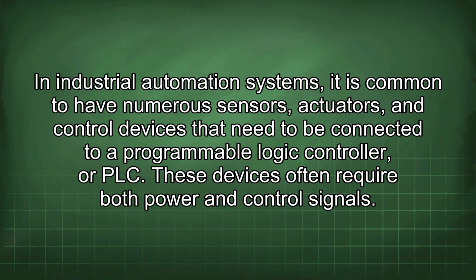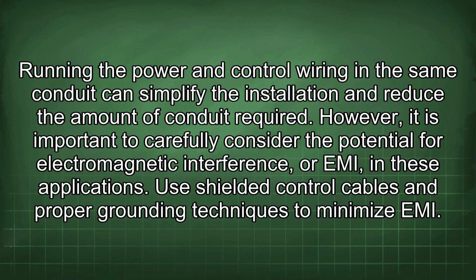In industrial automation systems, it is common to have numerous sensors, actuators, and control devices that need to be connected to a programmable logic controller, or PLC. These devices often require both power and control signals. Running the power and control wiring in the same conduit can simplify the installation and reduce the amount of conduit required. However, it is important to carefully consider the potential for electromagnetic interference, or EMI, in these applications. Use shielded control cables and proper grounding techniques to minimize EMI.